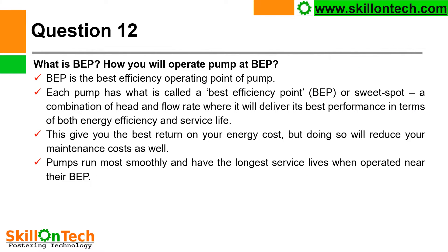Question 12: What is BEP? How will you operate a pump at BEP? BEP is the best efficiency operating point of the pump. Each pump has what is called a best efficiency point — BEP or sweet spot — a combination of head and flow rate where it delivers its best performance in terms of both energy efficiency and service life. This gives you the best return on your energy cost.